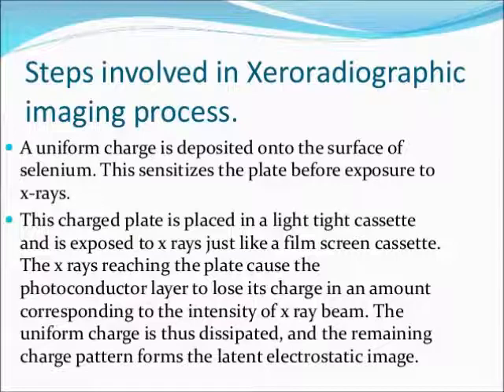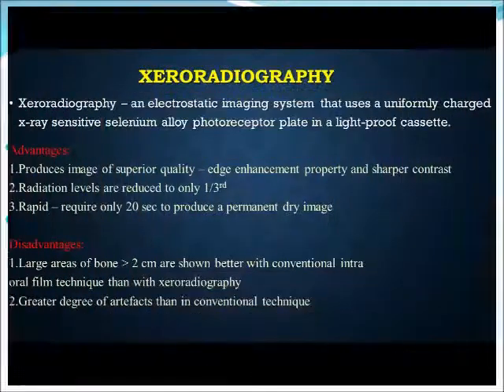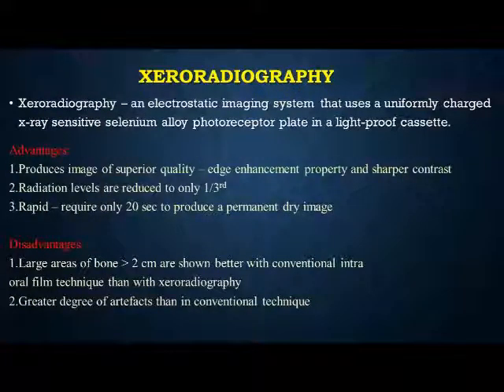Advantages of xeroradiography include producing images of superior quality, edge enhancement property, sharper contrast, radiation levels reduced to only one third, and rapid processing requiring only 20 seconds to produce a permanent dry image. Disadvantages include that large areas of bone greater than 2 cm are shown better with conventional intraoral film technique, and there is a greater degree of artifact than in conventional technique.